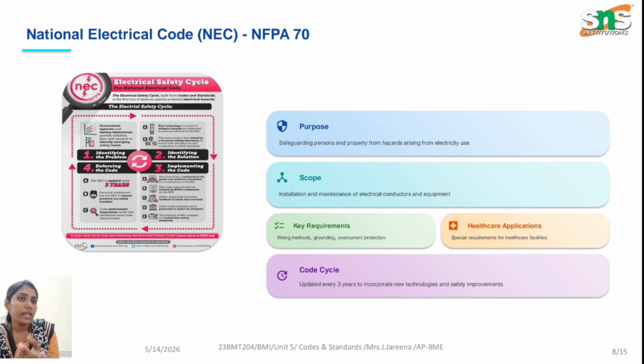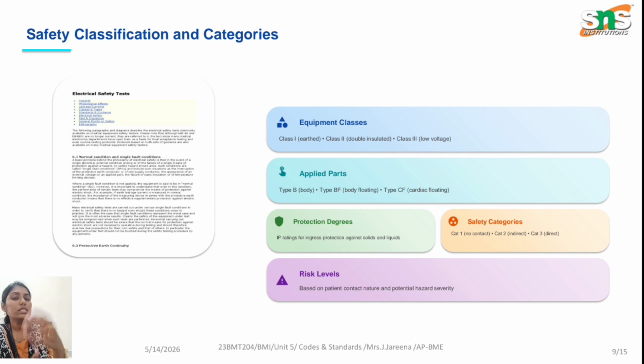The code cycle is given as once in 2 years or once in 3 years, but it depends upon the level of equipment, the advanced level of equipment. These are the safety classifications and categories. Based on the applied parts, we have three classifications: type B body, type BF body floating, and type CF cardiac floating. Equipment classes are class 1, class 2, and class 3. Class 1 is the earthed type, class 2 is double insulation, and class 3 is low voltage equipment. Based on the classification or the type of applied parts, we have different safety standards and protocols to be followed.